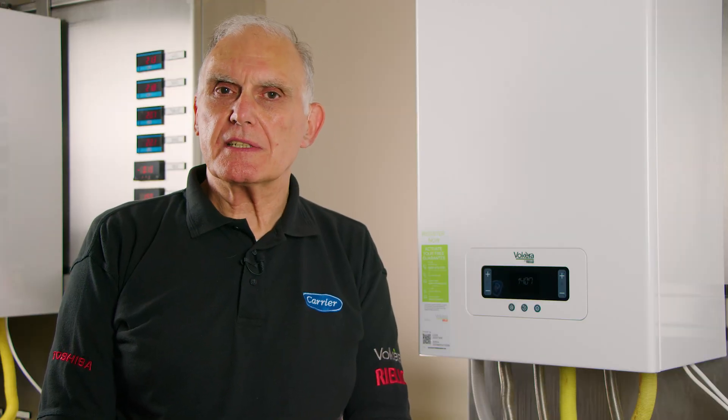In this short video, we'll be talking about how our Vokèra Synergy combination and system boiler range is commissioned after first firing. All Synergy models are equipped with our latest active combustion control — software and hardware that monitors the air fuel mix and optimizes it for best efficiency and minimal emissions.